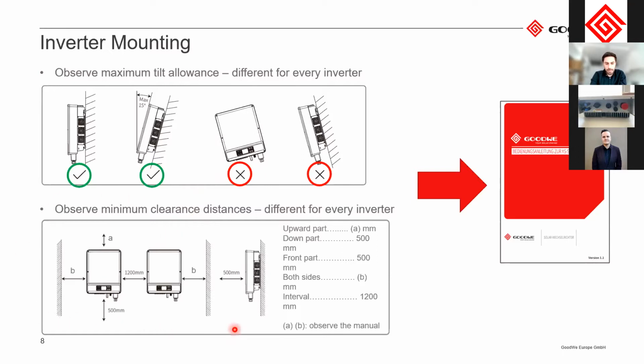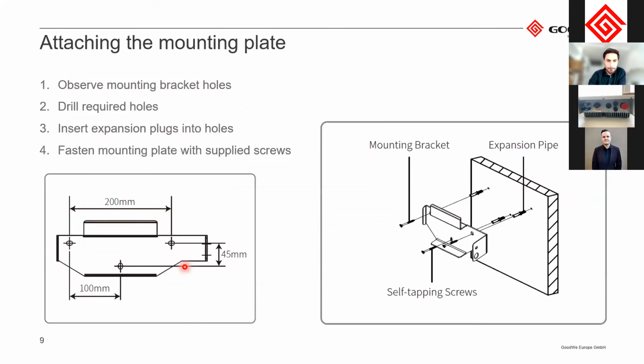Please also observe the distance between the inverter and any other object, either the next inverter or the wall. This can also affect the cooling system if it's installed too narrow. The specific distances for your inverter, whether it's an MT, a hybrid inverter, an HT or an XS, are all in the manual. When you know all this, it's time to mount the inverter on the wall. Please observe the holes in the mounting brackets. Then you drill the holes, insert expansion plugs, and fasten the mounting brackets before you hang the inverter and screw it on the side.